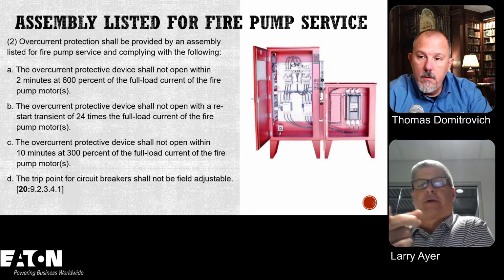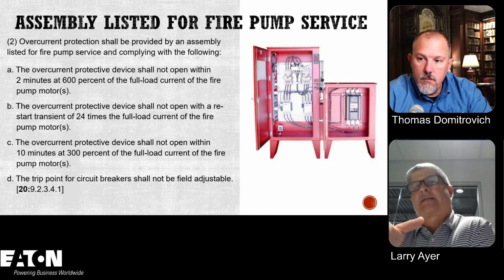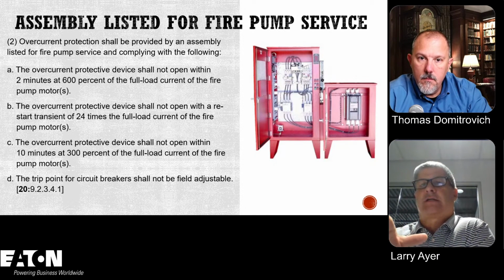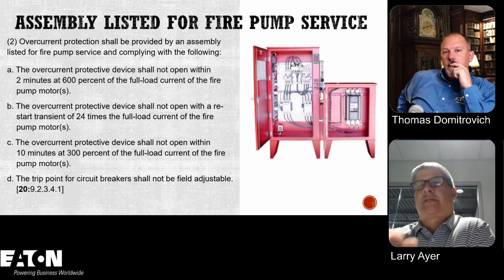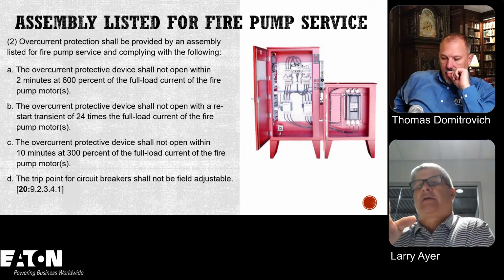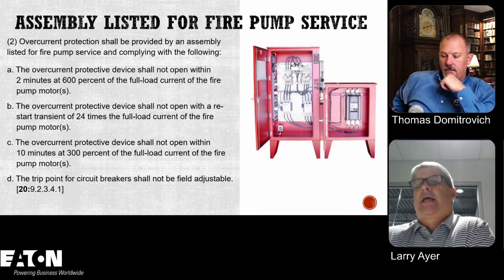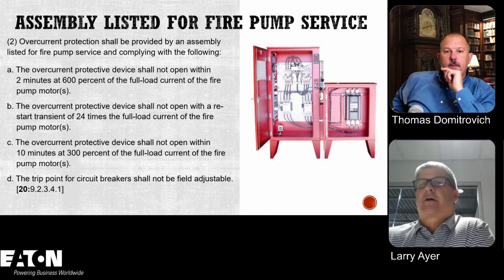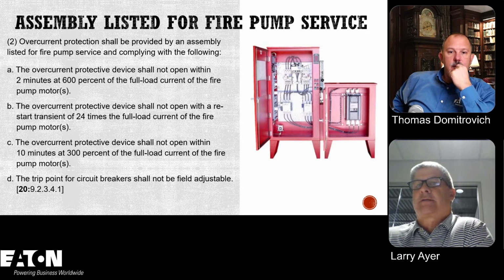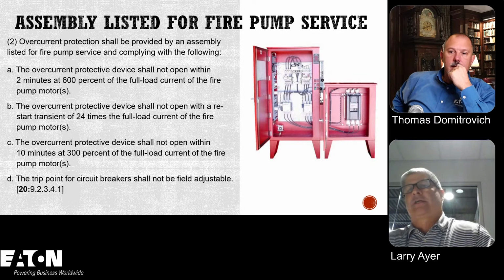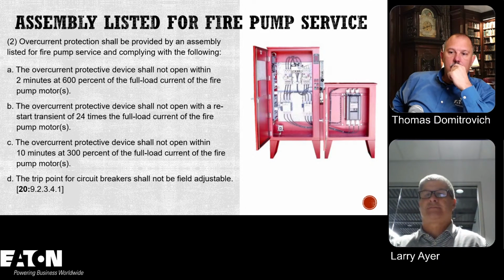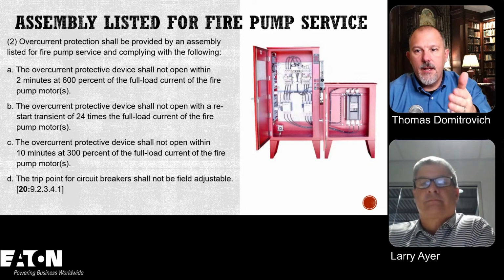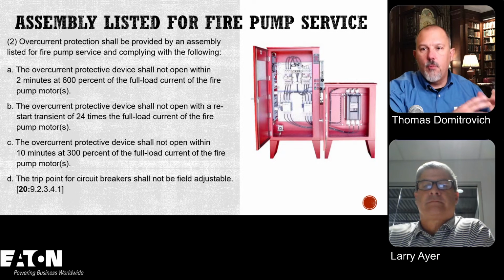Yeah, two things I want to go over here, and then I want to look back at Bruce's question. If you look at that assembly listed for fire pump service, they treat this differently than your disconnect. These are listed fire pump controllers that have been tested. The disconnect that's tapped off the service has to be able to carry locked rotor indefinitely. This talks about 600% of full load current for 2 minutes and things of that nature. So these are a little different, and they give you a little more leeway because these are listed components that have been tested at the factory. That's true. And then you would pick these controllers based upon the size of motor and whatnot that you have, and all of these considerations are probably handled as part of the listing.